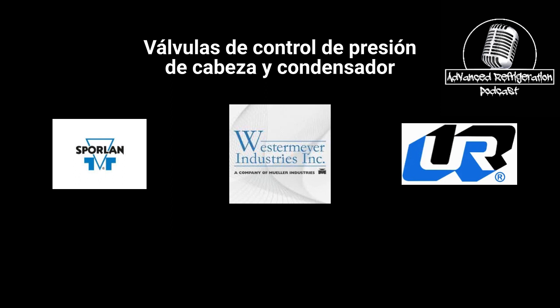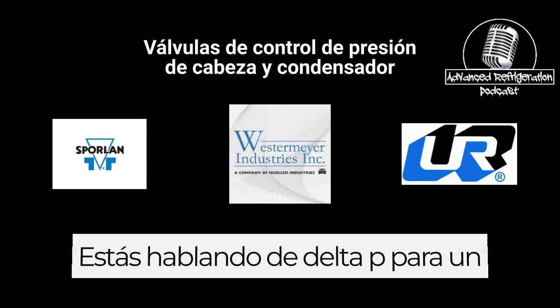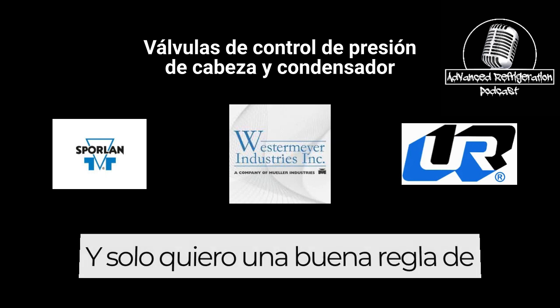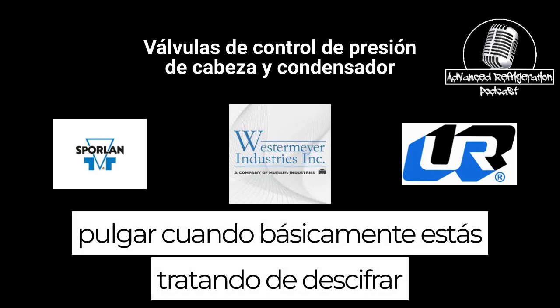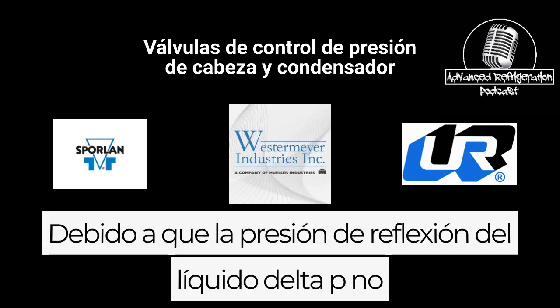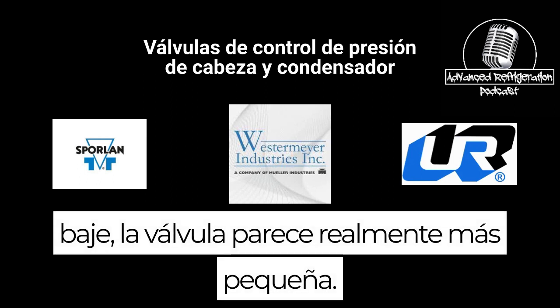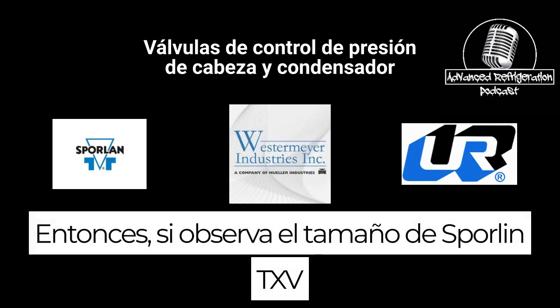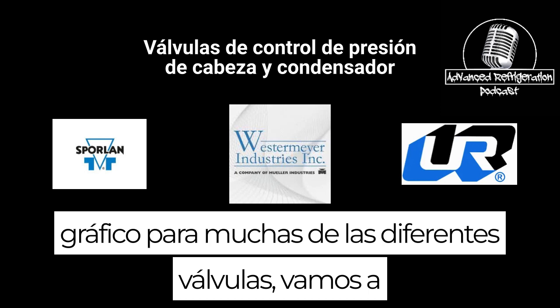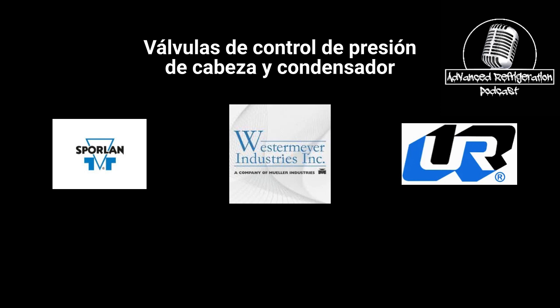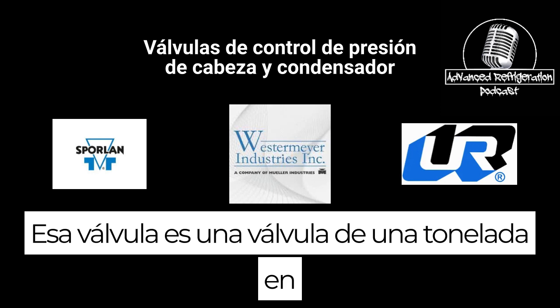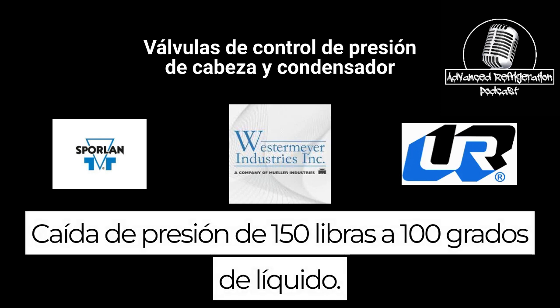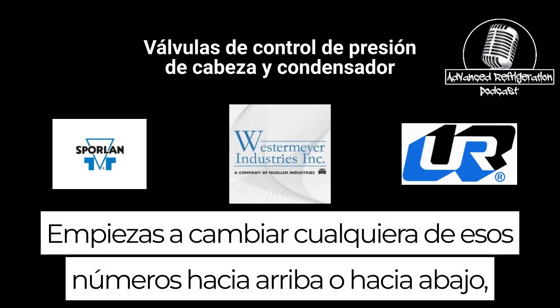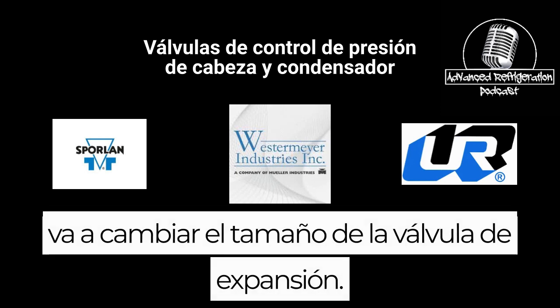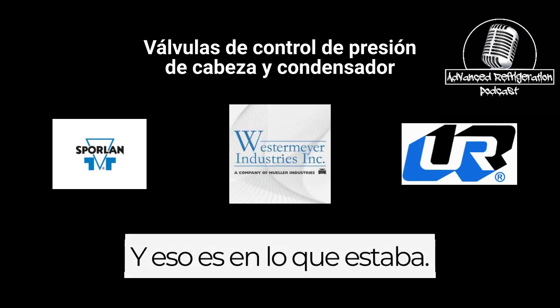Yeah, I do want to. You're talking about delta P for a second, like sizing the valve. I just want to give a good rule of thumb when you are trying to figure out what the valve is supposed to be, because with the delta P, as the liquid and suction pressure get lower, the valve appears actually smaller. So if you look at the Sporlan TXV sizing chart for a lot of the different valves, let's just say we're dealing with a 1-ton valve. Well, that valve is a 1-ton valve at 150-pound pressure drop at 100-degree liquid. You start changing any of those numbers, higher or lower, it's going to change the size of the expansion valve.